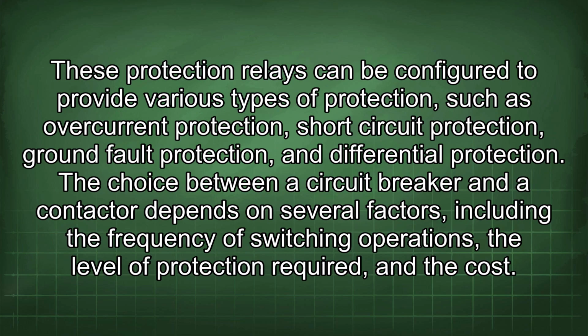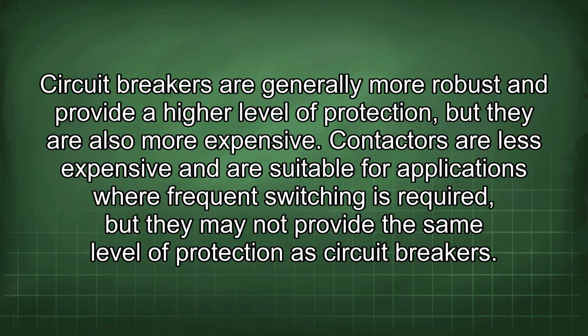These protection relays can be configured to provide various types of protection, such as overcurrent protection, short circuit protection, ground fault protection, and differential protection. The choice between a circuit breaker and a contactor depends on several factors, including the frequency of switching operations, the level of protection required, and the cost. Circuit breakers are generally more robust and provide a higher level of protection, but they are also more expensive. Contactors are less expensive and are suitable for applications where frequent switching is required, but they may not provide the same level of protection as circuit breakers.